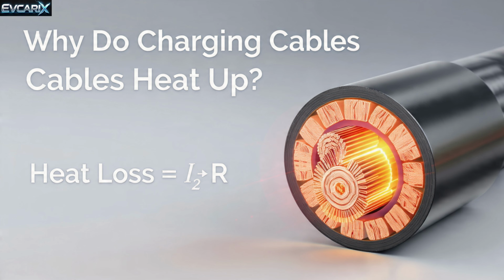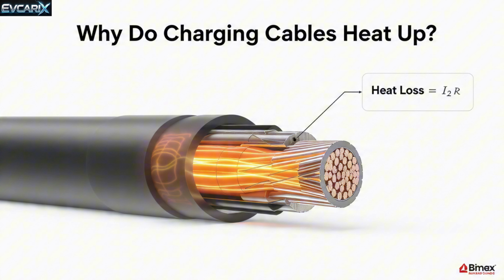So why do cables heat up, and why is this so important? The answer lies in Joule's law. P loss equals I squared times R. In other words, if current doubles, heat loss increases fourfold. This quadratic relationship is one of the biggest obstacles engineers face when trying to increase power in a 400 volt system. Let's talk with numbers. To carry 180 kilowatts, a 400 volt system requires 450 amps of current. And if we take that system as a reference, it produces 100% heat load. When you carry the same energy in an 800 volt system, the current drops to 225 amps, and the heat load falls to only 25%. That's a 4 times difference.